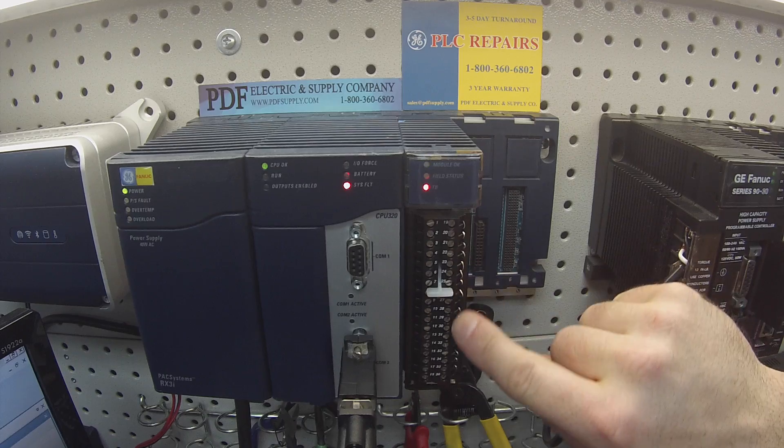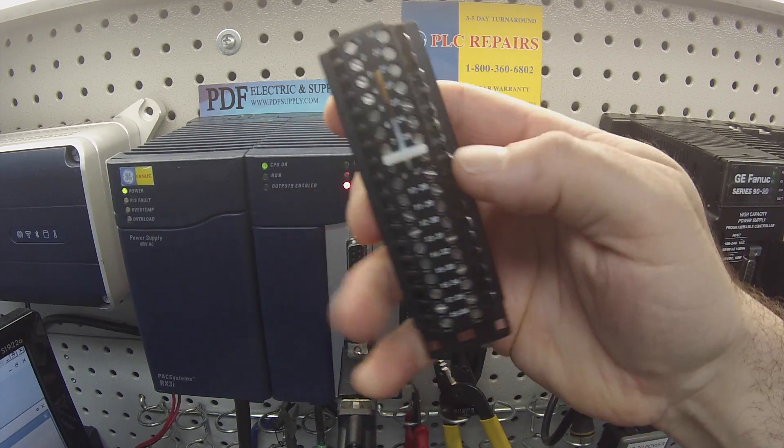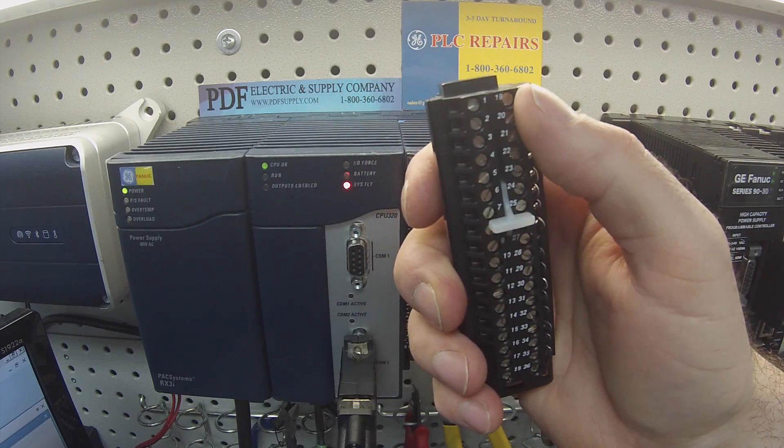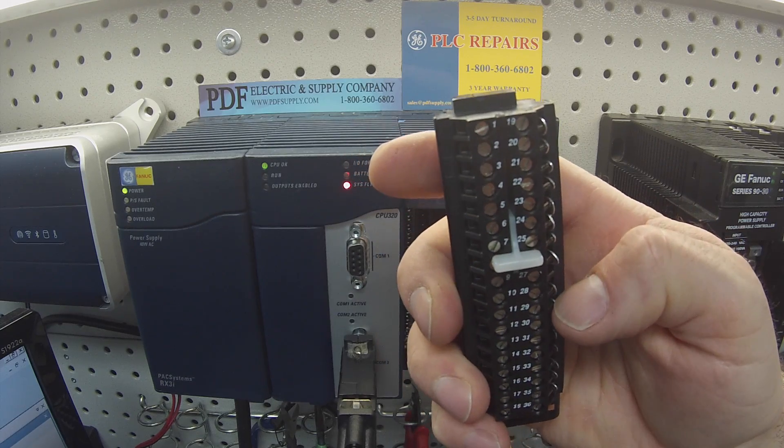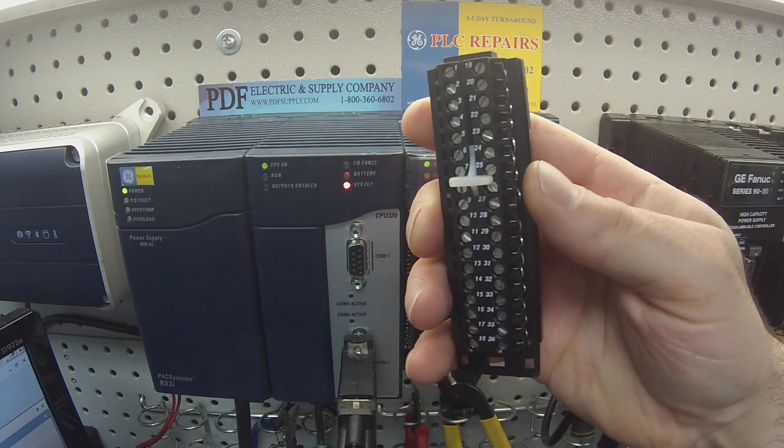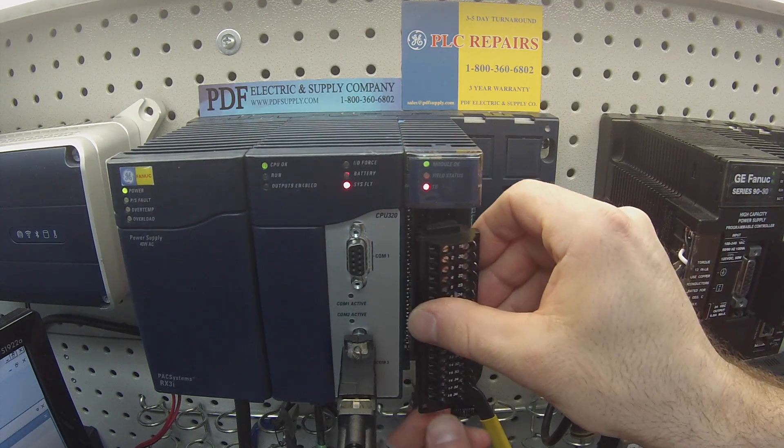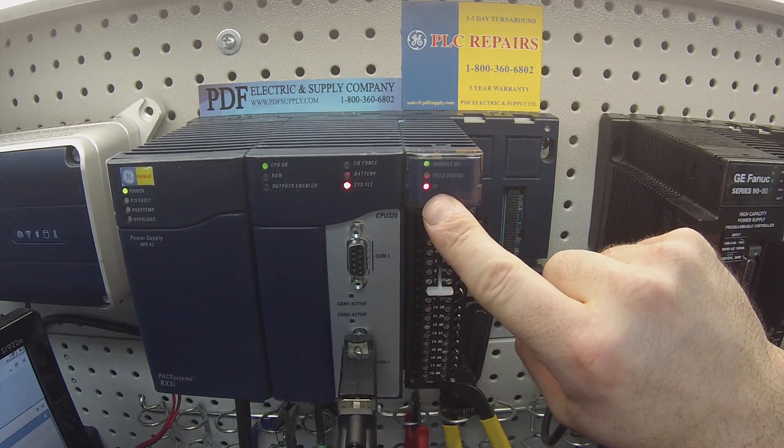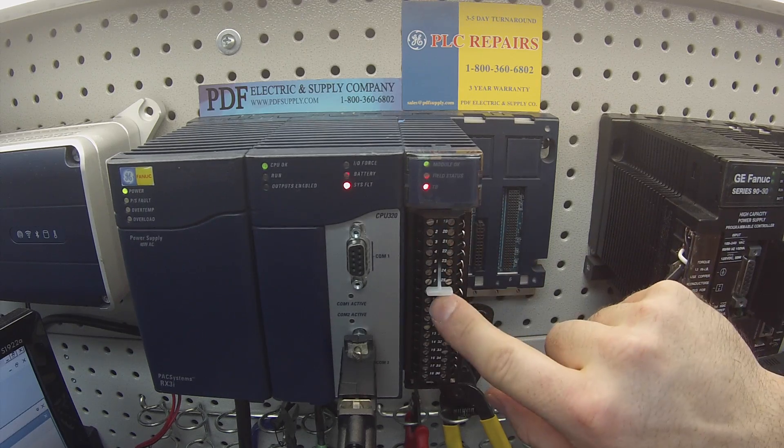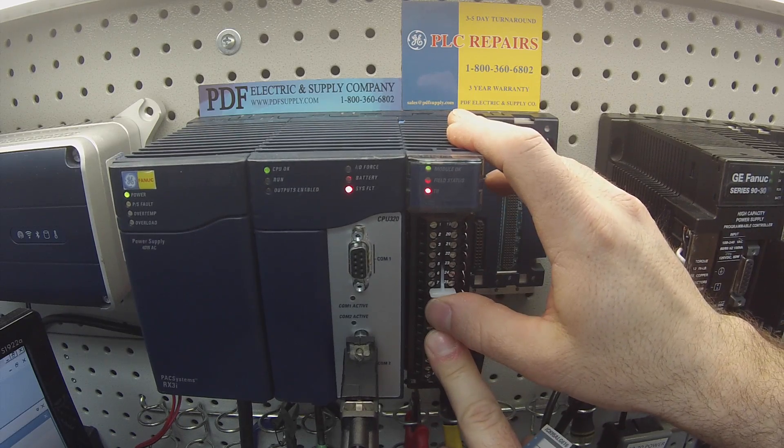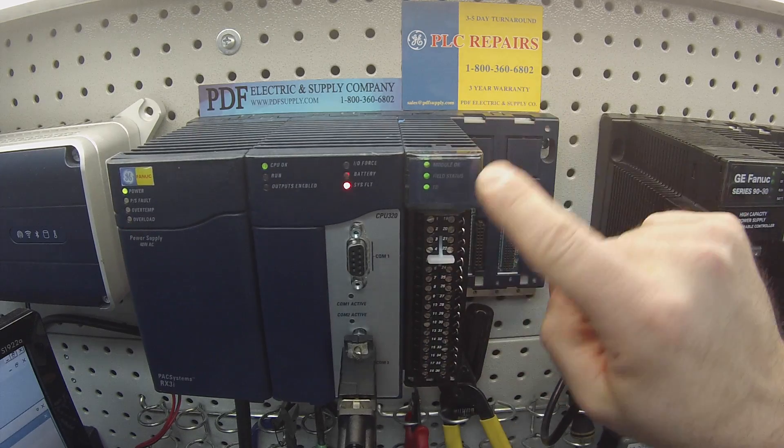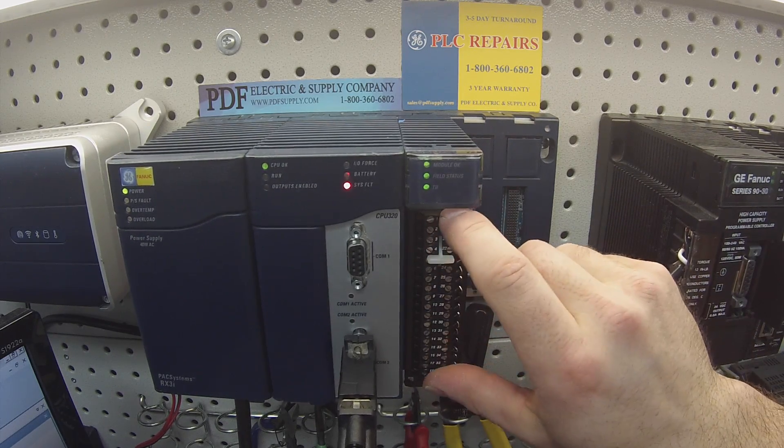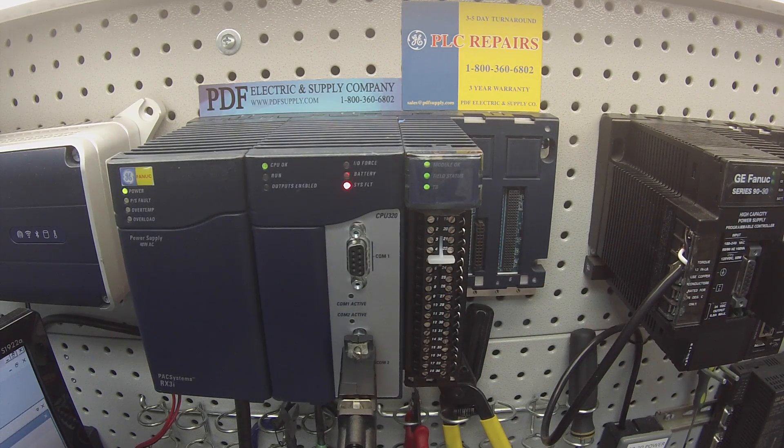You'll notice I have a terminal strip that I'm going to pull off to show you better. I have jumpers going down the right hand side from terminal screw number 19 to number 36, with the exception of number 28 which doesn't have jumpers. This is a high density terminal. I'm going to place it on the module itself. You'll notice my terminal block LED is red. That means the lever is not in the most upright position, which attaches it completely to make connection to the module. So I'm going to slide this up. Now my field status and my terminal block lights are both green. That means it's connected and it sees it.